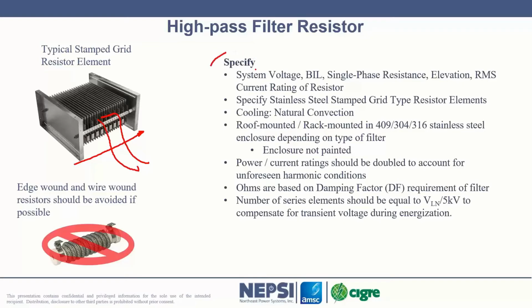These are what you need to specify, but generally speaking, BIL is important. What is the system voltage is another important one. Consider elevation effects. If I'm higher than, say, 1,000 meters, you want to make sure that you're considering the effects of elevation from a cooling standpoint, but also from an insulation, voltage insulation standpoint. Specify stainless steel grid resistors when at all possible, because they're just more resilient. These are what I would say bulletproof design. There's not much that can fail in that design, especially if you put some rating factor in there.